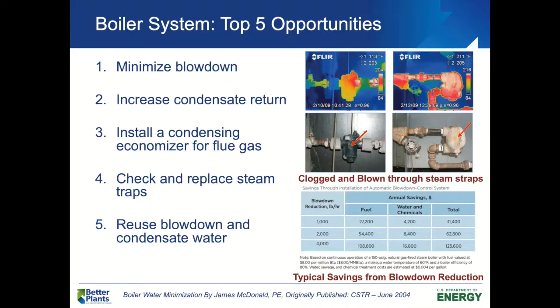condensate is not just water loss, but you are also losing the water treatment that went into the water, and also the heat energy that was put into this condensate in the boiler itself. So it is an expensive resource, and you want to make sure you return as much of it back to the boiler house. The third one I have is installing a condensing economizer for flue gas.